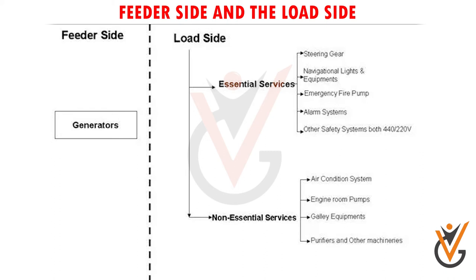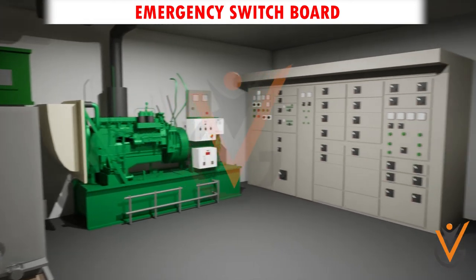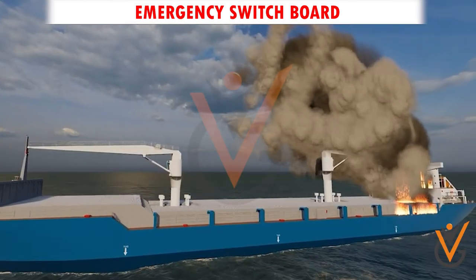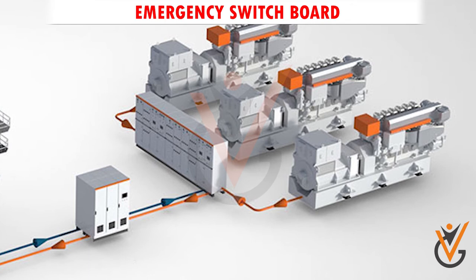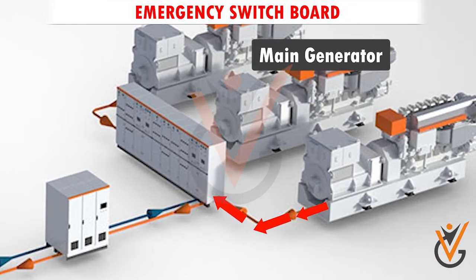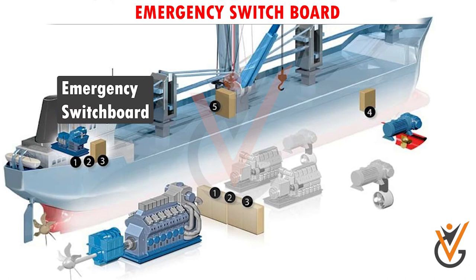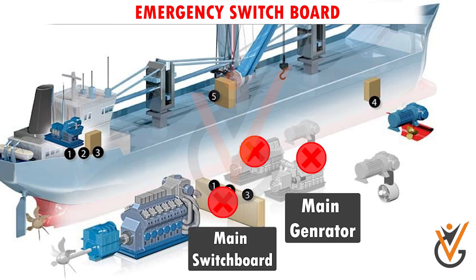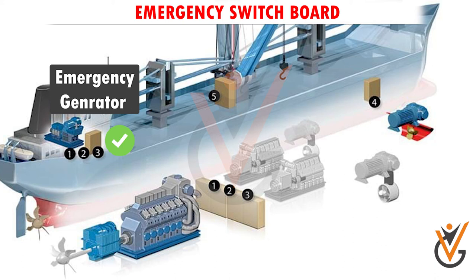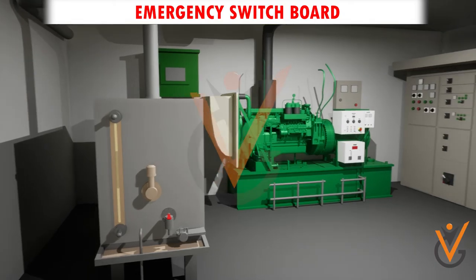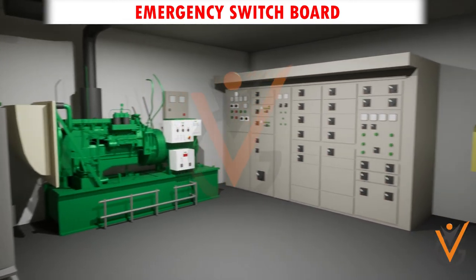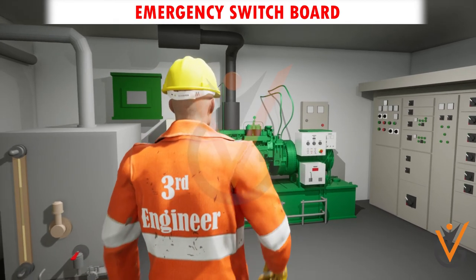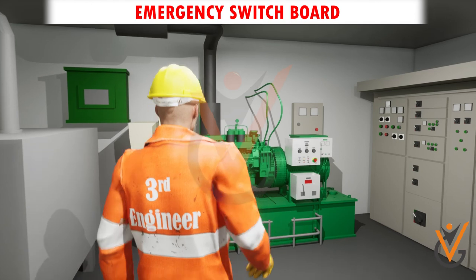The emergency switchboard supplies equipment and machinery essential during any emergency, like fire or flooding. During normal operation, power is supplied from the main generators to the main switchboard, and the emergency switchboard gets its supply from the main switchboard. When the main generators fail, the main switchboard loses its supply, causing the emergency generator to start automatically and supply the emergency switchboard, ensuring critical equipment and essential services are always maintained for the safety of the ship and personnel.